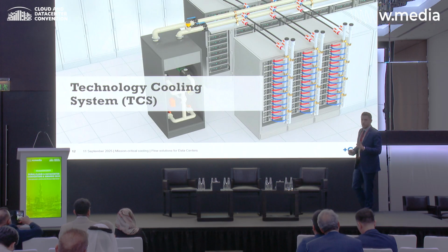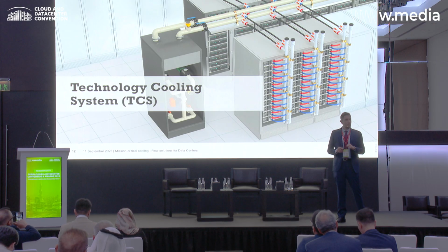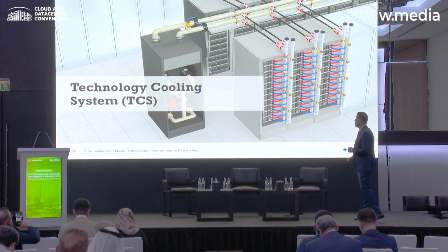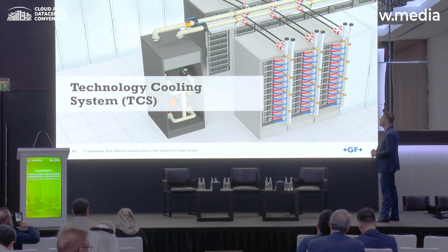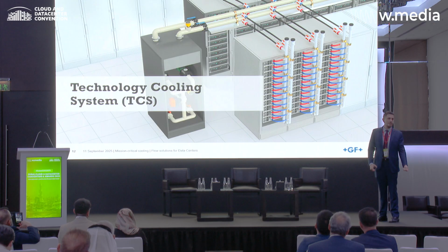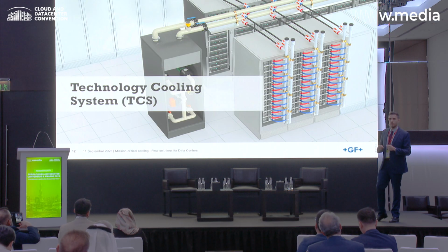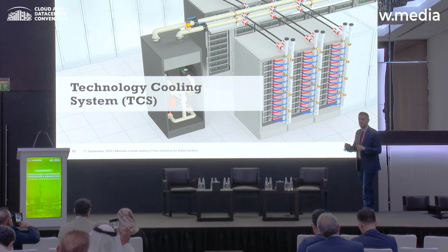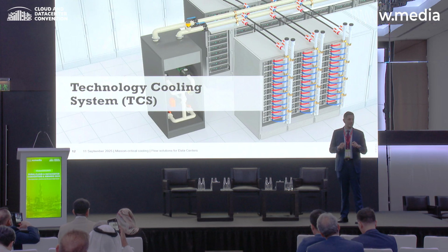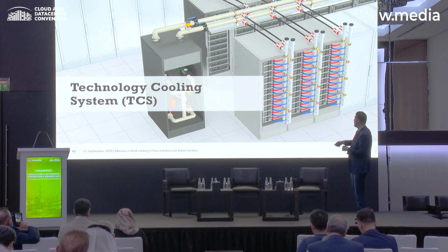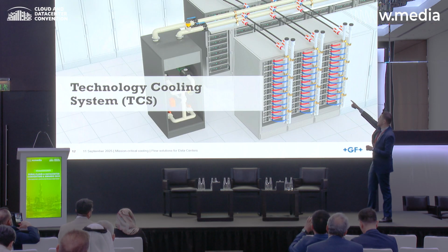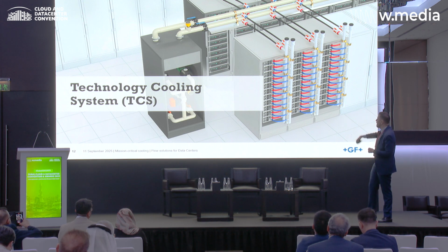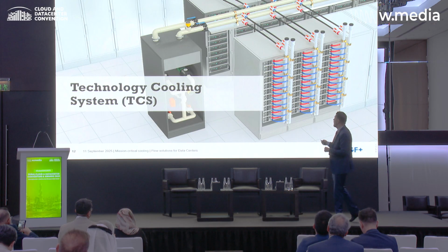Now moving from the chilled water system to direct liquid cooling, to the technical water. As you can see in this photo, we were a bit futuristic and saw this era coming a few years back, making sure every component in your technical water network is non-metallic - from the distribution lines to the butterfly valves to the quick disconnect valves, which we'll see in a second, to the ITE rack manifold.